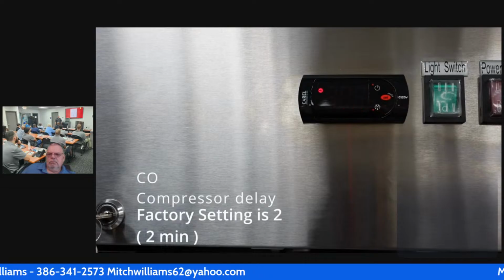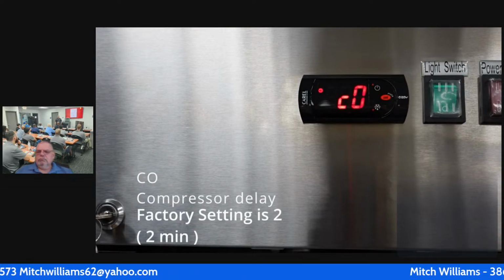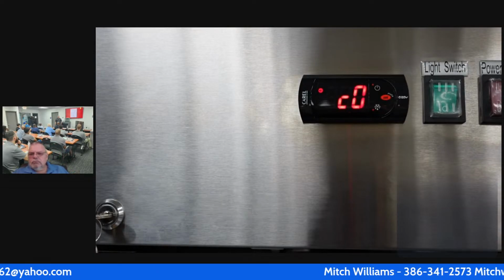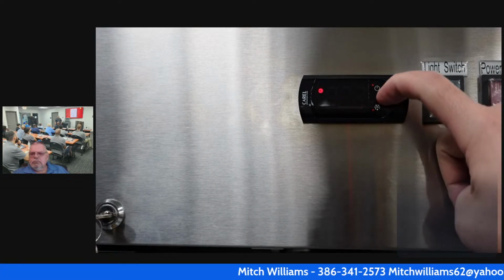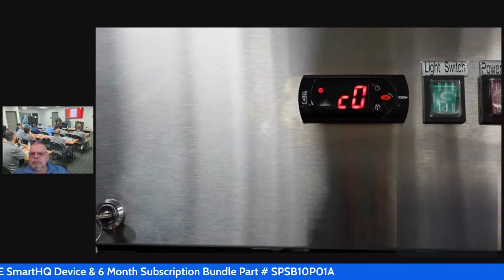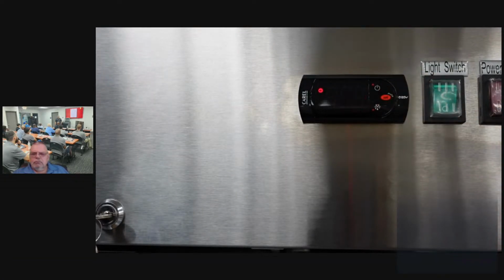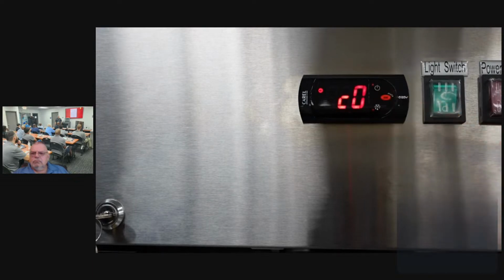The next parameter we'll see is C0. C0 is the compressor delay. The factory setting is 2, meaning once you start the unit, the compressor will not turn on for 2 minutes. This will help protect the electrical components of the compressor.